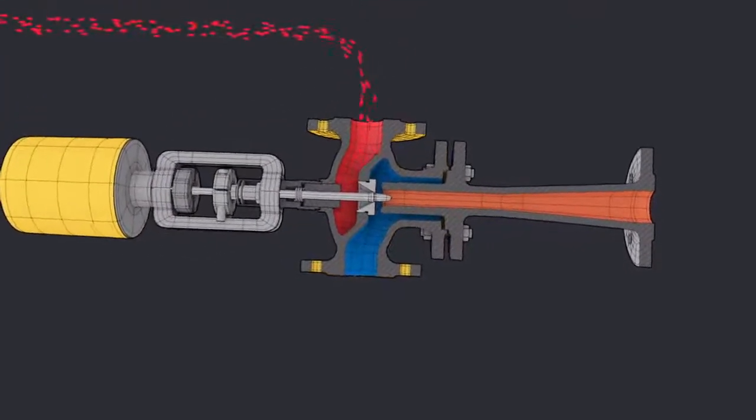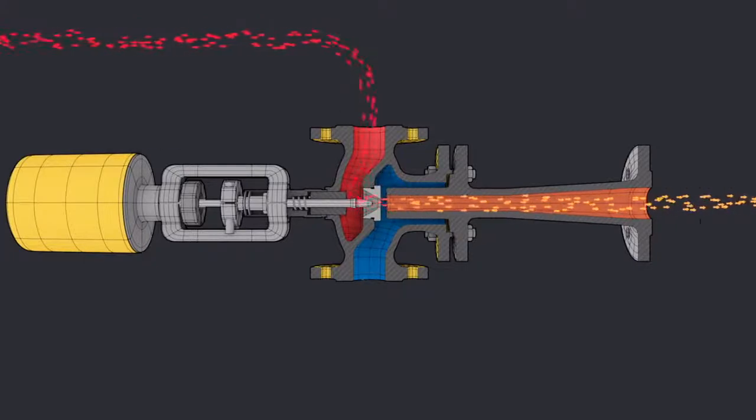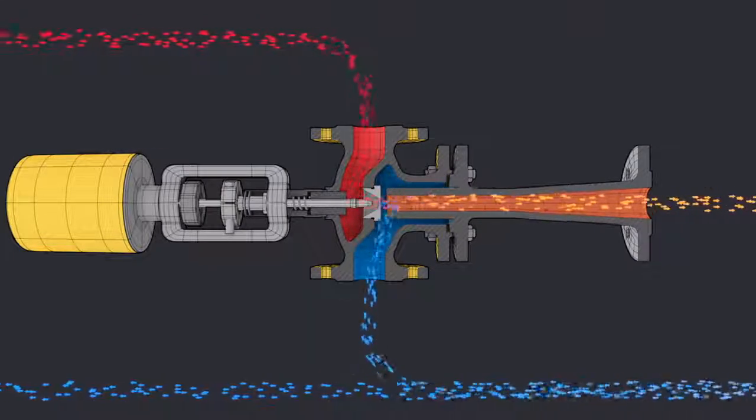Heating water flows in and is accelerated where the nozzle tapers down. The increased flow velocity causes a local drop in pressure so that return water can be drawn in.